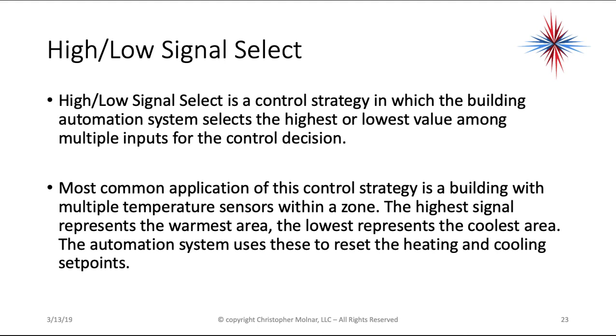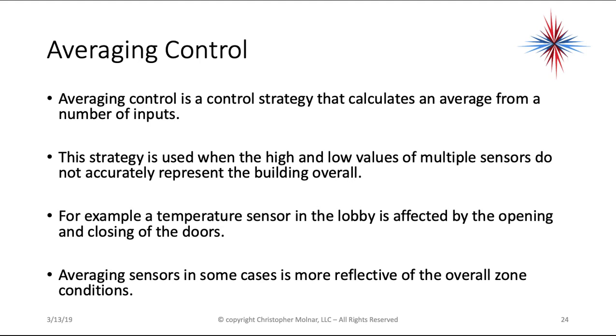High and low signal select is a control strategy in which the building automation system selects the highest or lowest value among multiple inputs for a control decision. The most common application is a building with multiple temperature sensors in a zone — the highest signal represents the warmest area, the lowest the coolest. Averaging control collects an average from a number of inputs, used when high and low values of multiple sensors don't accurately represent the building overall — for example, a lobby sensor affected by door openings.